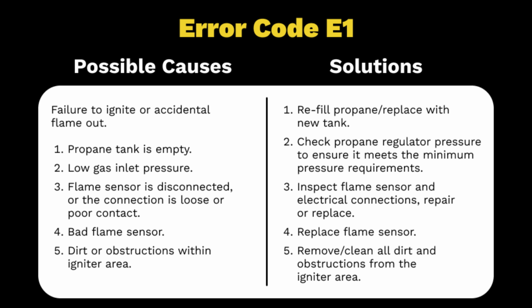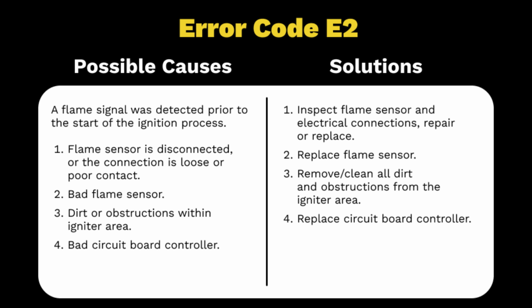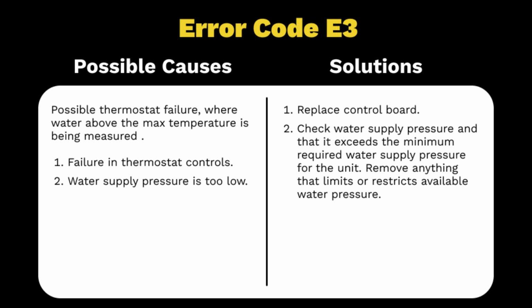purge this. If an error code of E2 displays, this means that a flame signal was detected before the ignition process started. We want to ensure that the sensor is properly connected and clean. If an error code E3 indicates, it's a possible thermostat failure with water above the maximum temperature being measured. This can also be caused by too hot of ambient water coming into the unit, but more often is related to the water flow. We want 1.5 gallons per minute flowing through the system at a minimum.